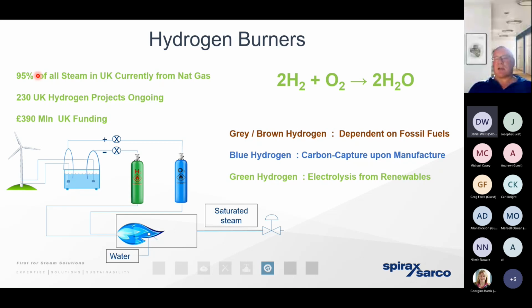Now, Spirax Sarco, we're not combustion experts, we don't pretend to be, but we have been working with a number of steam boiler and burner manufacturers here in the UK to identify that if and when our client is in a position to produce green hydrogen on site, then it may simply be a case of removing the existing natural gas burner from the steam boiler and replacing it, retrofitting it with a new hydrogen burner.